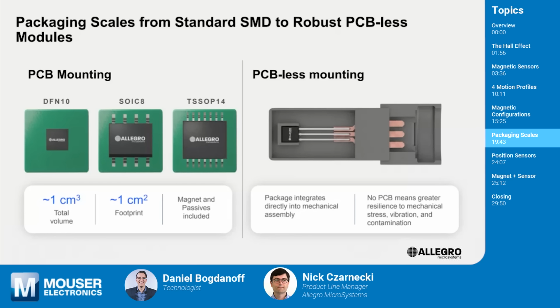Actually it's for small designs in a lot of cases. We see this a lot in harsh media applications, industrial and automotive especially. PCB-less is popular for several reasons: it's more robust to the environment, you don't have to worry about vibration, and you weld the terminal leads directly to a connector lead frame. You can encapsulate or pot the sensor so it's immune to oil or fluids. You get very good EMC performance because we integrate the capacitors needed for transient suppression inside the package. You can also make it very small and thinner, since you don't need a PCB. Finally, you simplify your supply chain — you don't need a contract manufacturer to build a PCB, or any external components. You simply buy the one sensor, put it in an application, weld the leads to the connector lead frame, and you're basically done with a nice sensing solution.